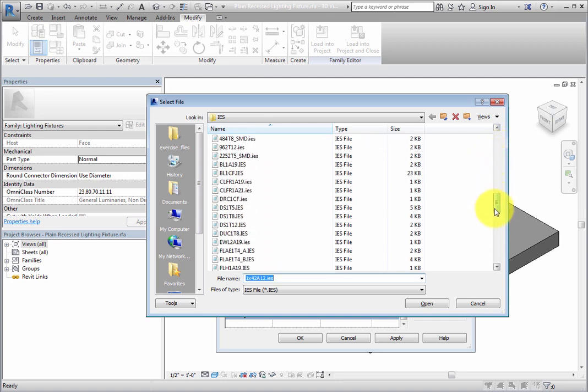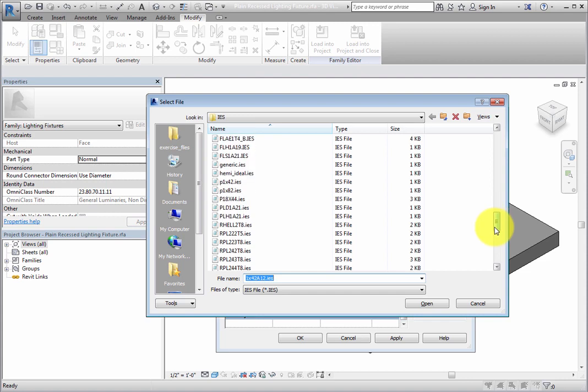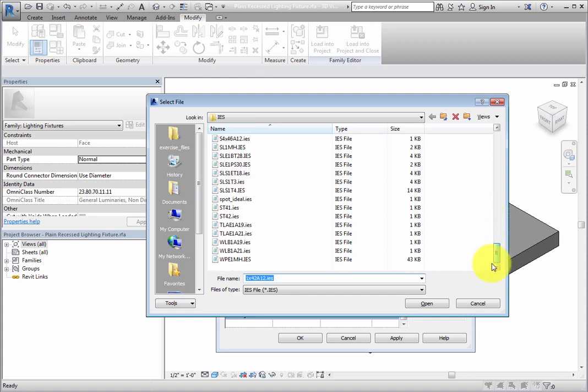You can use one of the IES files available in the Revit library, or you can ask the lighting manufacturer to provide you with an IES file. These files contain the measurement of the light distribution out of the lighting fixture.